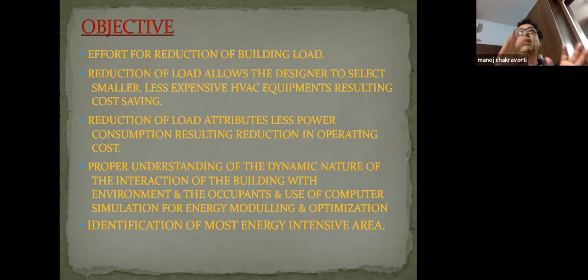As far as the building is concerned, there will be a lot of computers and other electronic gadgets, so we should also simulate their load. Once we simulate that load along with the building simulation, we can correctly find out the HVAC requirement—whether we really need 1,000 tons, or 600 tons, or 800 tons.